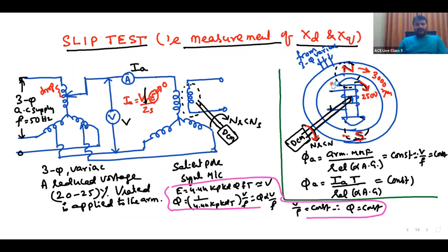About 1/4, almost 20%. The reluctance power during this test is also less. That is also one reason why we give very little voltage: if you give rated voltage, the reluctance torque will be more, and reluctance torque being more means opposition will be more. But during this, we are applying some 20% V, so the reluctance power will be less.